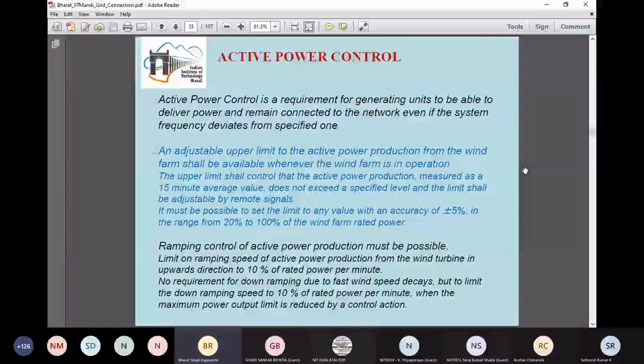This slide gives whatever I have discussed here, which says how much adjustable upper limit is available. We can see that an accuracy of plus minus 5% is there, in a range from 20 to 100%. Then ramping control is also there, which says that in the upward direction the power should not be increased by more than 10% of rated power per minute. So this is how the ramp increase in active power when the wind is blowing can be exercised. Next slide, please.